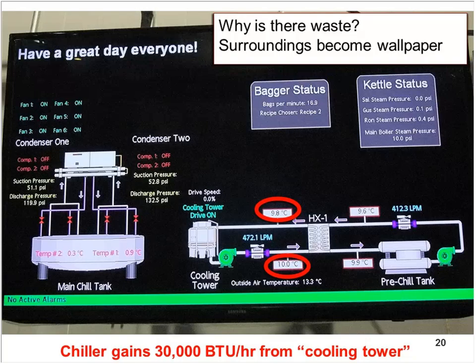If you look at what's circled, the information is telling you that you have 9.8 Celsius water going to your cooling tower, and after the water is cooled by your cooling tower - I'm using hand quotations for 'cooled' there - it actually ends up at 10 Celsius, or warmer. So in another respect, the factory is using their cooling tower to bring heat from the city of Edmonton into their chiller system, where they're then using electricity to remove that heat. It's a continuous loop.